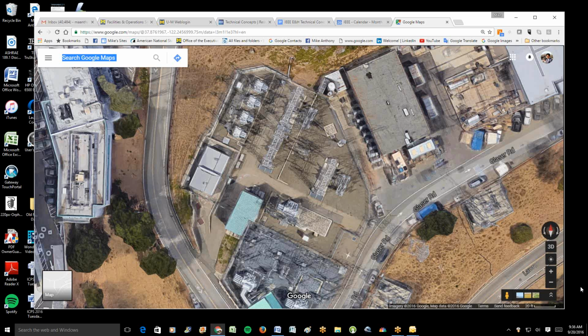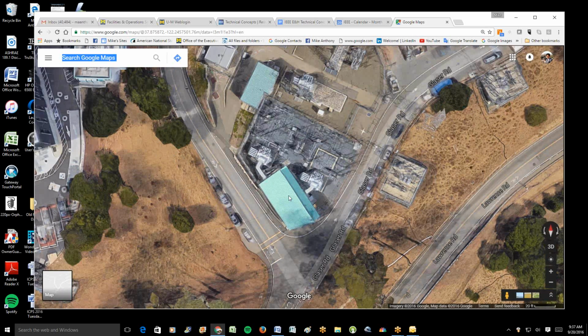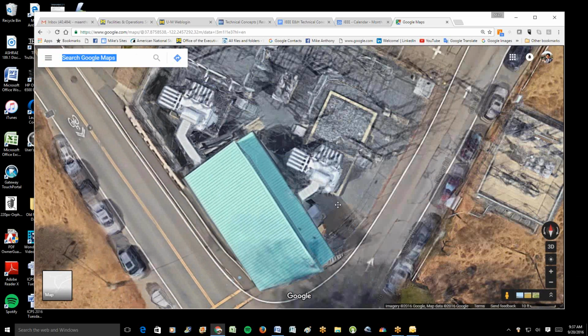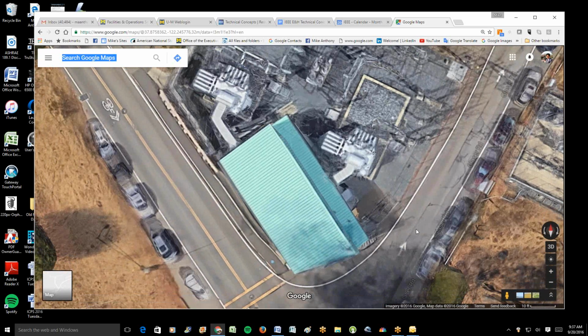Those transformers were replaced in about 2001, when we remodeled or refurbished this yard, just before DOE basically took it over. The yard that is ours was the original PG&E yard, and it fed both UC Berkeley and the Lawrence Berkeley Laboratory. After PG&E divested and sold off a lot of this stuff, UC and DOE purchased it, and then about five to six years later, UC Berkeley built the substation you see in the lower part of the screen -- they call that Hill Area Sub. After they built that, they were able to use our 1247 tie line between the two and feed the laboratory while we remodeled the Grizzly Peak area, which was the original.